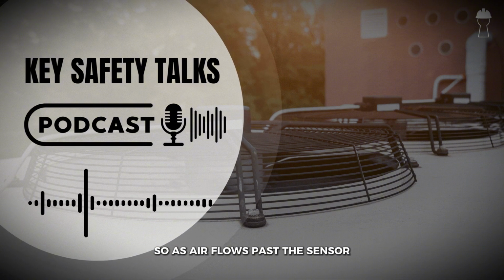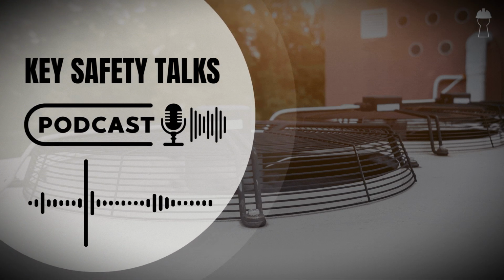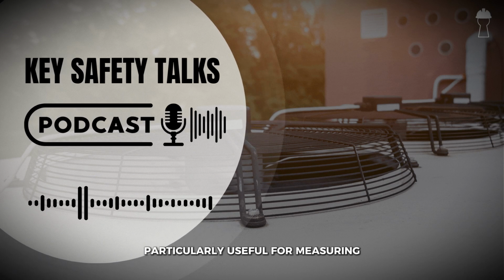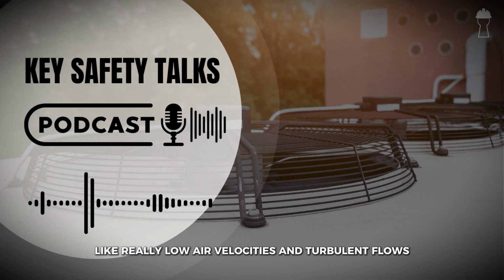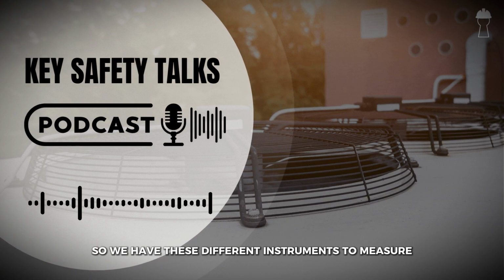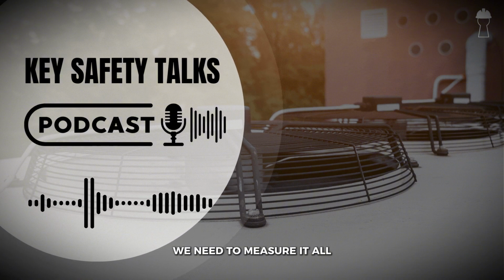So as air flows past the sensor, it cools it down. And that rate of cooling is proportional to the air velocity. Thermal anemometers are particularly useful for measuring really low air velocities and turbulent flows. So we have these different instruments to measure airspeed, air volume, and even air turbulence. Right. We need to measure it all.